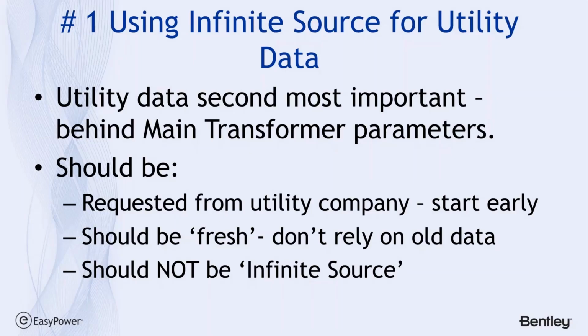Just as a matter of course, as soon as you accept responsibility for doing an arc flash, you should be addressing the utility company and explaining what you're trying to do, so it's not a matter of holding them at large for any reason, just data that you need to do the study. But the thing I want to emphasize here is that you should not use the infinite source. If you use the utility icon in building a one-line diagram with EasyPower, it automatically has very high numbers in it, which we reflect as the source, an infinite source that has its purpose, but not as an arc flash value.